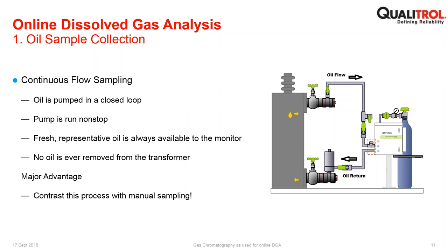Just to go into a little bit more detail on some of the points in the last slide. Oil sample collection: typically, for an online system, it will be continuous. Oil will be pumped through some type of closed loop, taken out of the transformer at some sampling point, illustrated here by a high-level sampling point, through a monitor, and then pushed back into the transformer. And this is usually a continuous process, right? So you've always got fresh oil going through the monitor for gas extraction initially, but ultimately for analysis and ultimately for diagnostics. It happens with online monitors continuously.